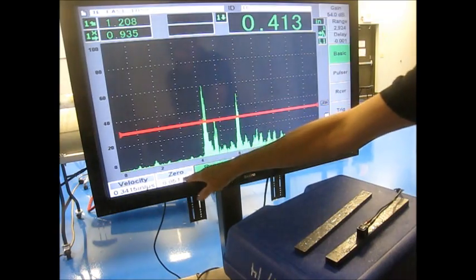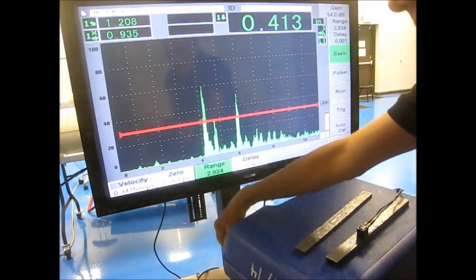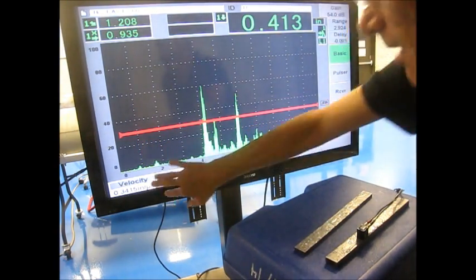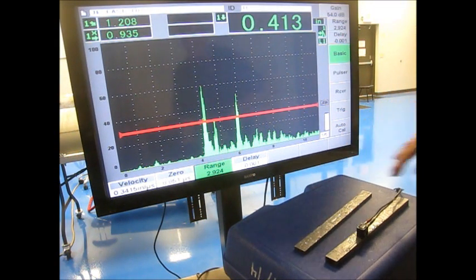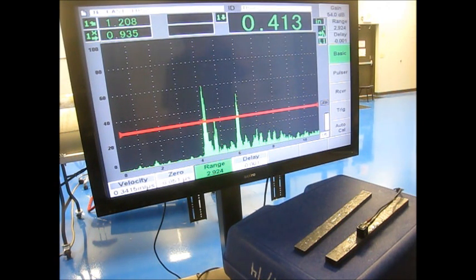So something that's 100 thousandths deep will be at the one line, 200 is at 2. But the velocity is way out, because I really had to stretch it out. So, you're not going to be able to use your surface distance minus x value function to do any surface distance measurement.